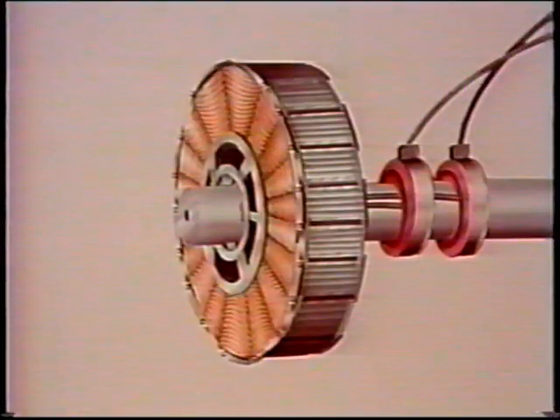Now, in order to understand how the rotor does this, we need to take a closer look at a typical rotor of a synchronous motor. A typical rotor has insulated coils or windings that are wound around steel projections. The projections with their windings are often called pole pieces, and when direct current flows through the rotor windings, the pole pieces become electromagnets with fixed north and south poles. The number of magnetic poles on the rotor of a synchronous motor equals the number of magnetic poles in the stator of the motor. Direct current is generally supplied to these rotor windings from an outside power supply through slip rings and brushes.